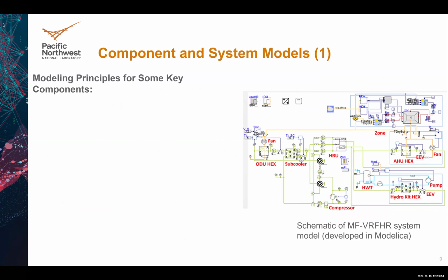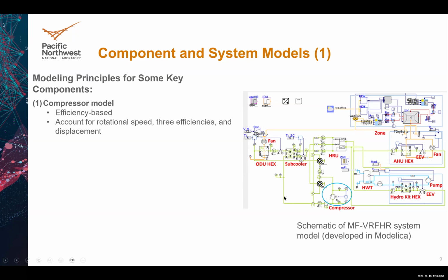So I will start with the modeling work first. This is a complex system, right? You have one outdoor unit, you have two indoor terminals. Also, you have a unique device, the heat recovery unit. So how can we model these systems? Here you can see a schematic of this system we developed in Modelica, relying on the Buildings library and the TRL library. Here I will show you some critical components we used for the modeling. First one is the compressor. This is an efficiency-based model that accounts for rotation speed, three efficiencies, and displacement.